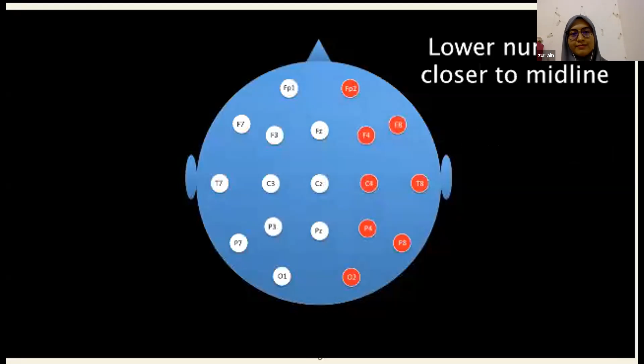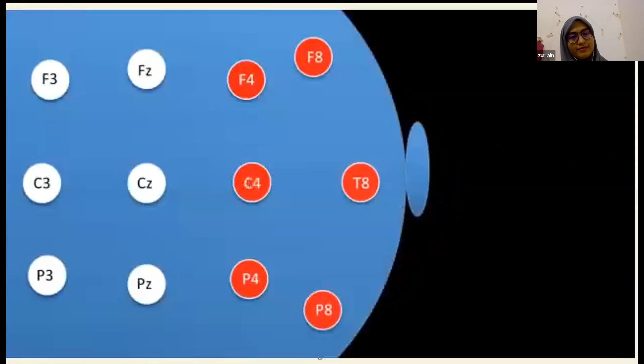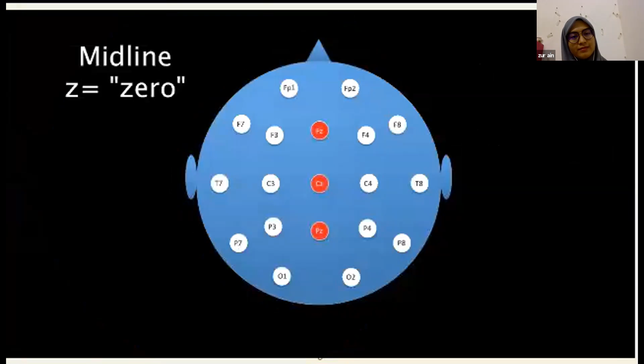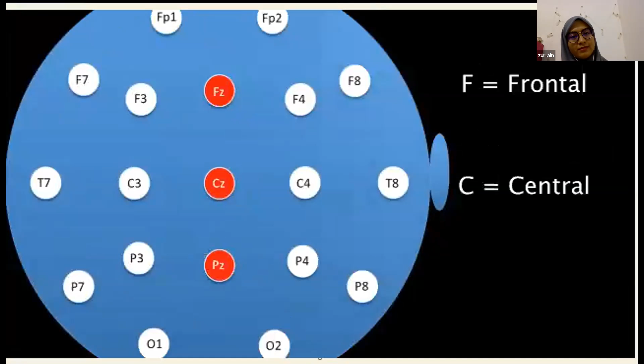Once all of these marks have been placed, the electrodes can be applied to the scalp of the patient. The electrodes are labeled as is shown here. The system is very simple, and each electrode is represented by letters and a number. The numbers indicate the side of the head, so that odd numbers are on the left side and even numbers are on the right. In general, lower numbers mean that the electrode is closer to the midline, so you can see here that C4 is closer to the midline than T8. And the midline itself is represented by a Z, which stands for 0. The letters are indicators of the position on the head. In this central chain of electrodes, you can see that the F stands for frontal, the C for central, and the P for parietal.